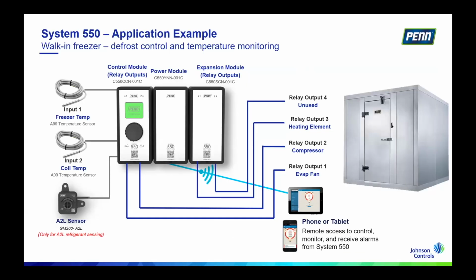Again, if you're hooked to the cloud here, you will get alerts and notifications by either email or SMS text or both that you have an issue with the system, a refrigerant leak. Since these are smart A2L sensors, they're communicating with System 550 via Modbus, so you're going to know exactly why this system went into mitigation. If there's a leak, it's going to tell you the A2L level through the sensor, and it's also going to tell you when the leak actually tripped the sensor, and then when it actually went back into operation. So that's where this is more of a smart system with the Modbus backplane.